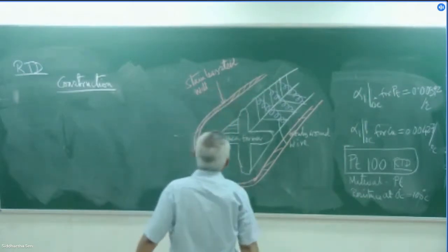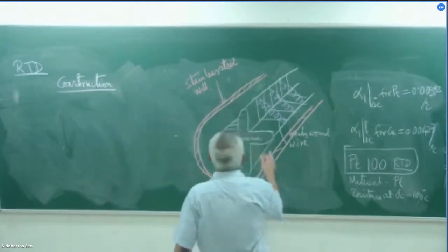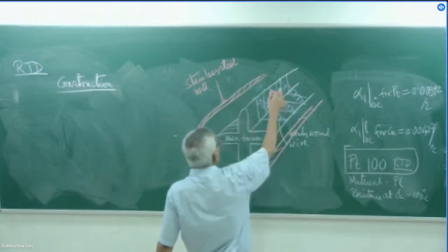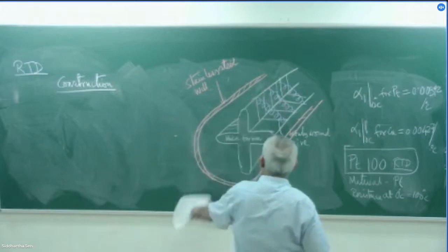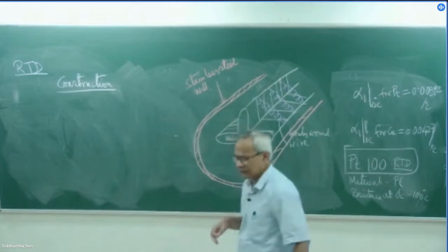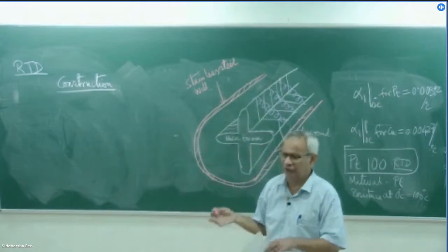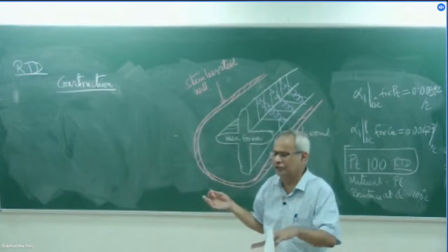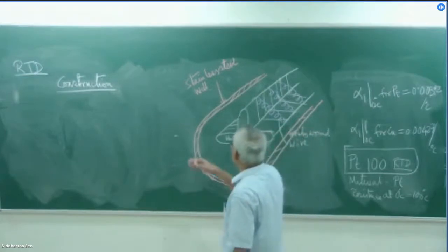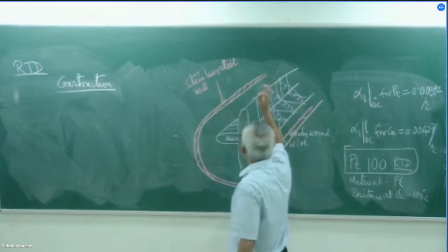That means a stainless steel tube is there, and everything is enclosed inside it, so that this stainless steel tube or well can be inserted inside a furnace, an oil furnace, or any boiler, so that external flame or soot or other things do not damage the area.